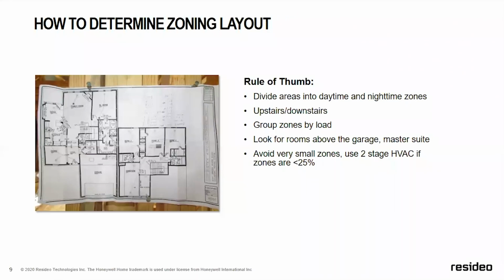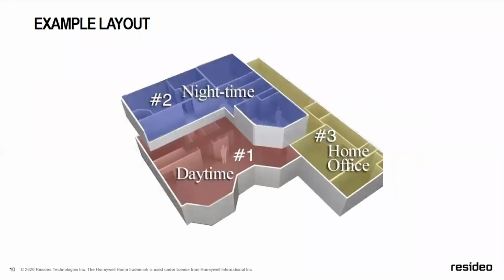Always avoid zones less than 25% of the total load. If you do have small zones, we highly recommend that you use 2-stage equipment. If you are doing zoning, you should offer upgrades. It's just a smart thing to do. An example of a layout: you've got your daytime, nighttime, and home office.